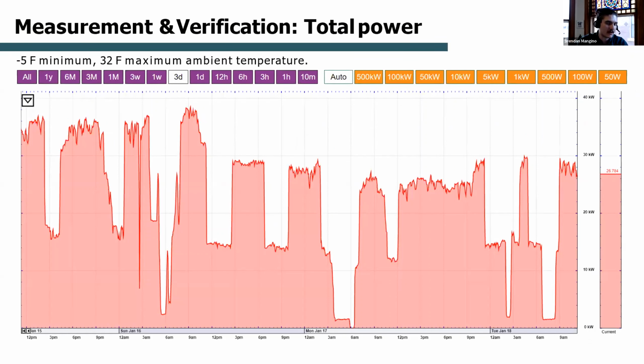And this is just the total power. So you can see that some of the heat pump arrays are staging on. You can see when it goes to 50%, that's one half of the system turning on because one tank got a little bit colder than the other one. These should be in harmony, but this just kind of shows that the system isn't fully balanced yet.